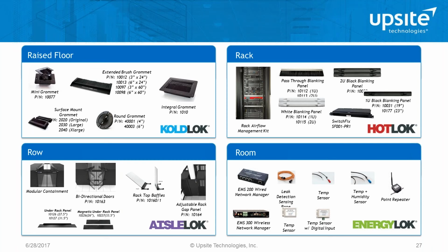For example, these aisle containment products could be purchased day one to make improvements, and then as cabinets are rearranged and shifted into more hot/cold aisle alignment, and gaps between cabinets are closed, the containment can flex along with those changes in the room.